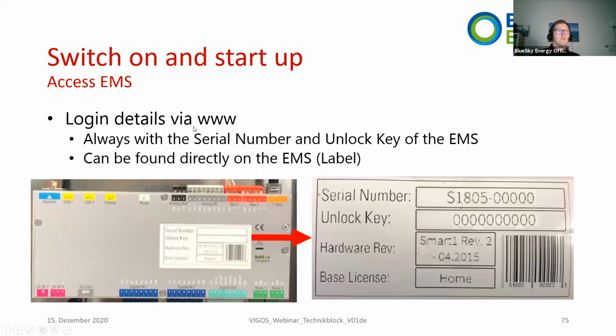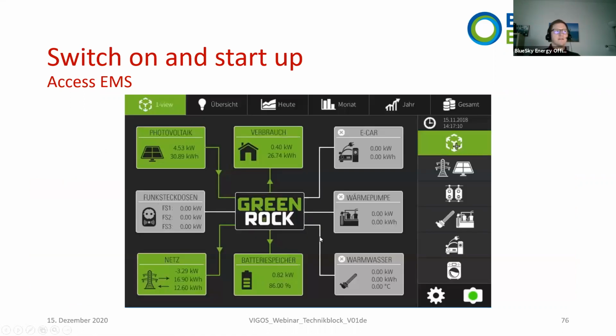And when you connect via the web, with live.mygreenrock.eu, you need a serial number and an unlock key. Both values are placed on the Vigos EMS. So you need to open the housing, and then you have a label on the Vigos EMS where you can see the serial number and the unlock key. And then the visualization will look something like that. Not in the same way, but this is the system which we are running now for our GreenRock systems. I hope you have heard from them or have seen something from them. So the visualization of the Vigos will look in the same way like we have here, or in a comparable way.